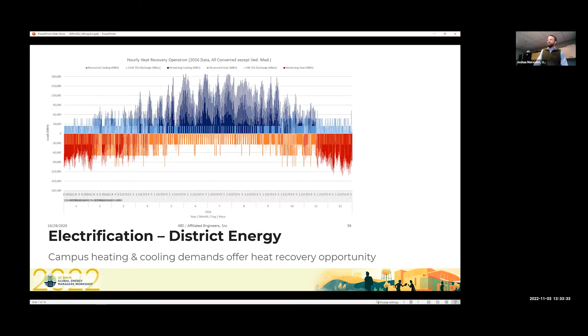But when you tie into a hot water system with heat recovery chillers or heat pumps, you can step that up to a useful heat temperature. This chart shows that about 60% of our heating load can actually be met with heat recovered from our cooling system. So for us, that became the big opportunity — we've been looking at this for about the past 10, 12 years, and it's exciting, we've got some action on it now.